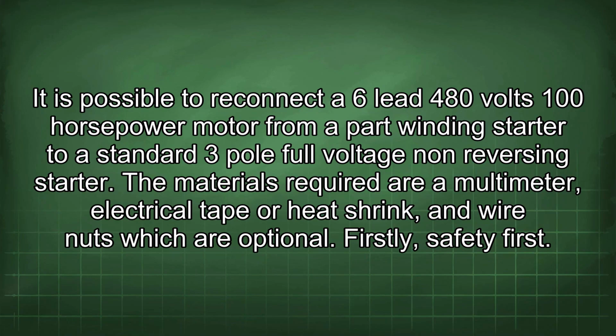It is possible to reconnect a 6-lead 480 volts 100 horsepower motor from a part winding starter to a standard 3-pole full voltage non-reversing starter. The materials required are a multimeter, electrical tape or heat shrink, and wire nuts, which are optional.